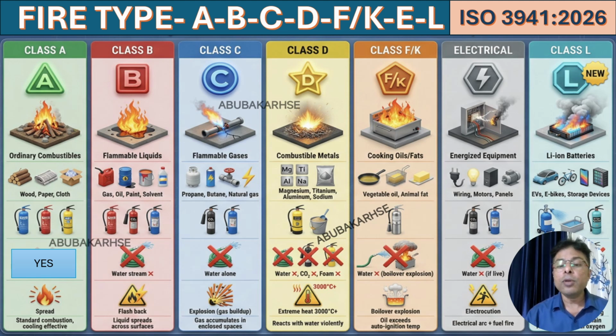For this fire extinguisher, you can use the CO2 fire extinguisher or the wet chemical powder. Don't use water. If you put water, it will suddenly explode, so don't use water. The impact is boil-over explosion, when the oil exceeds its auto-ignition temperature.